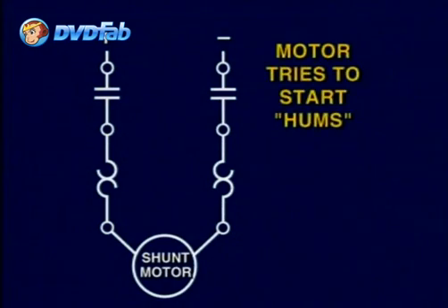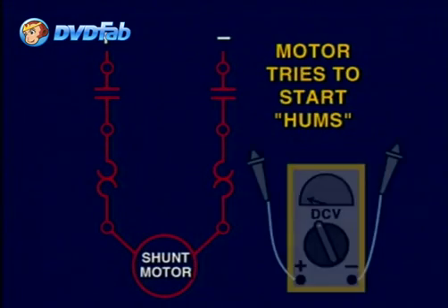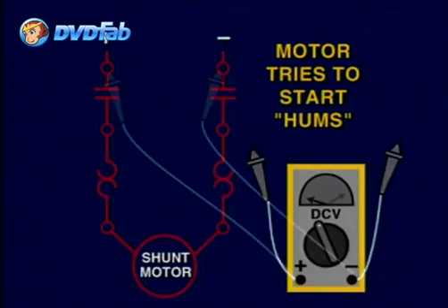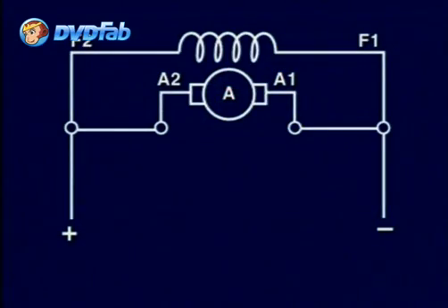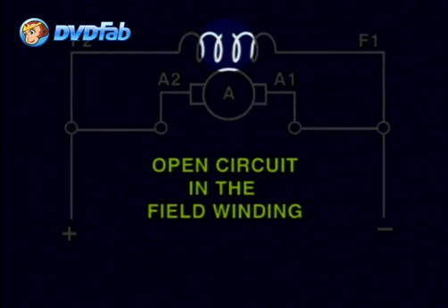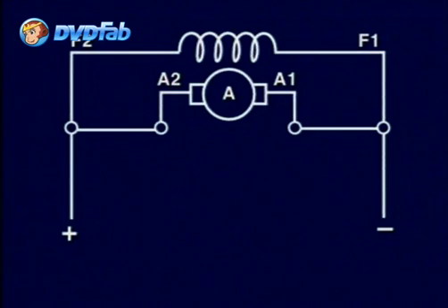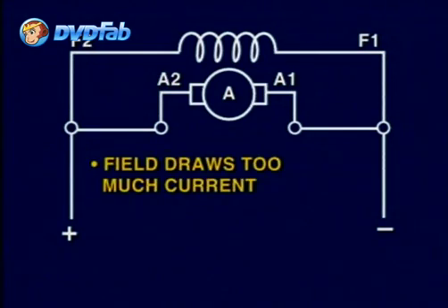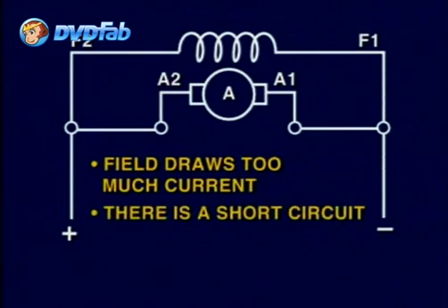If there is a loud humming sound, it implies that it is trying to start and has supply voltage present. First, check to make sure that the supply voltage is at the correct level. Otherwise, the problem most likely lies with an open circuit in the field winding. This open circuit can exist if the field winding draws too much current or if a short circuit occurs in the insulation in the coils.